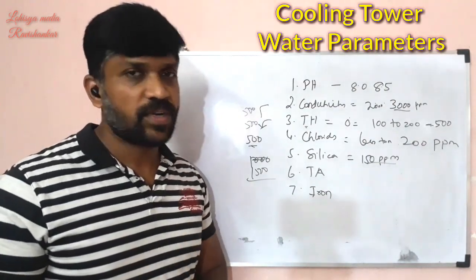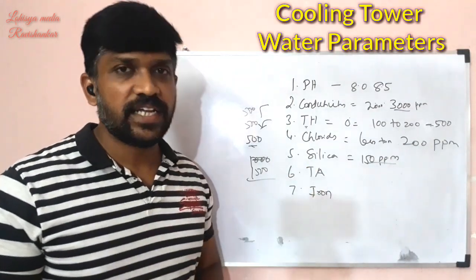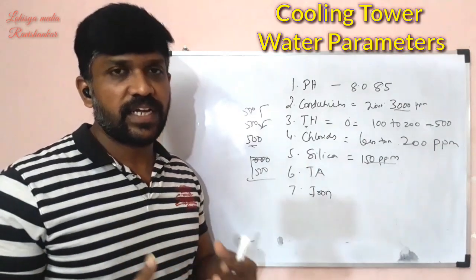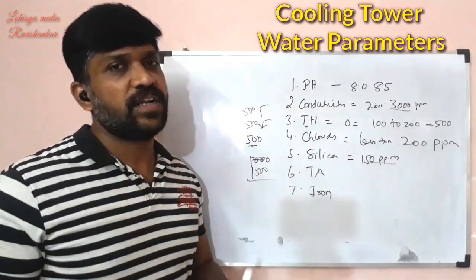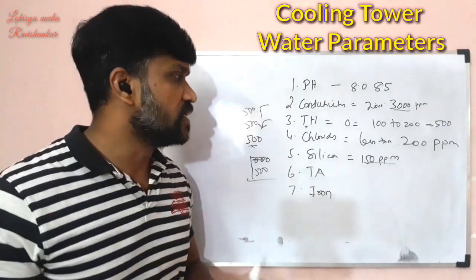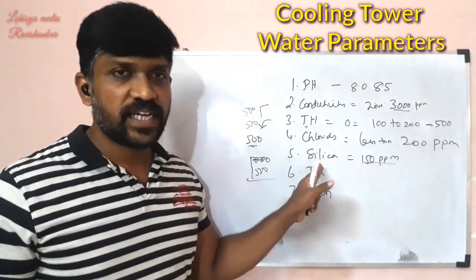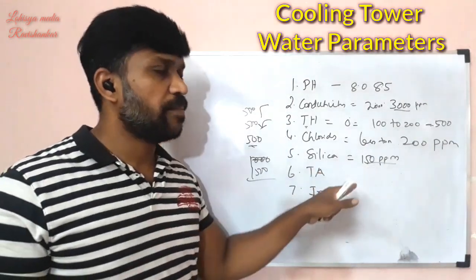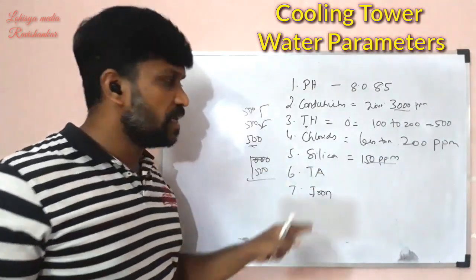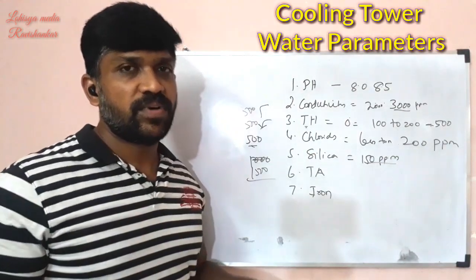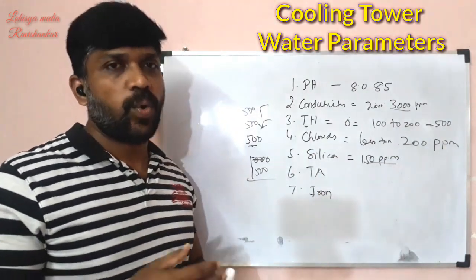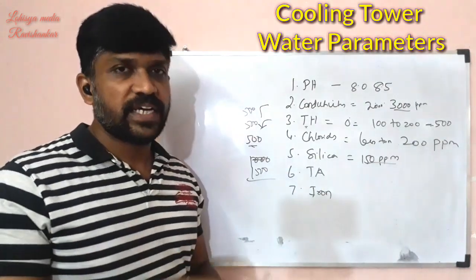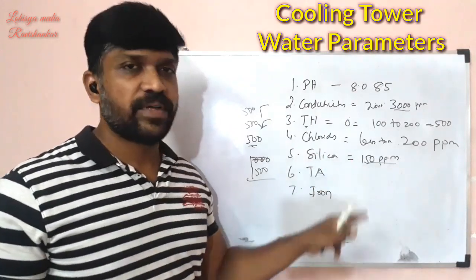Calcium scaling is a long, gradual process, but silica scaling is very hard to treat. Silica scale appears white in color and is very difficult to remove. This is why we maintain silica below 150 PPM and use silica inhibitors to prevent silica scaling in the cooling tower.